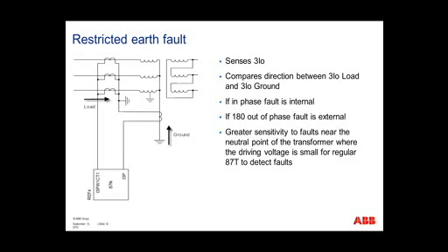Restricted earth fault protection. Here is an example of a protection scheme that typically was not done in the solid state realm. It has been introduced with the microprocessor-based relays. What restricted earth fault does is protect against faults that are close to the neutral leg of the transformer. For instance, if you have a fault on the neutral, say at this point right here, I hope you can see my mouse, you're going to have no voltage drop. So it'll be very difficult to see any change in your zero sequence current.